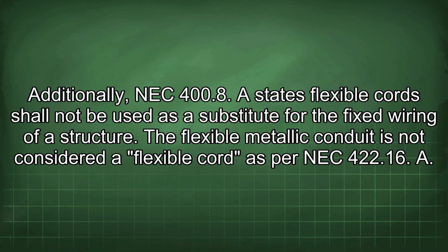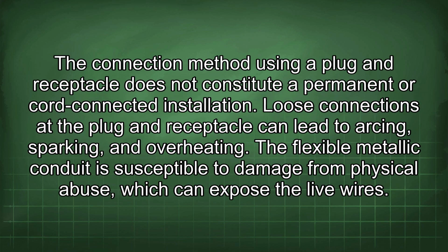Additionally, NEC 400.8 states flexible cord shall not be used as a substitute for the fixed wiring of a structure. The flexible metallic conduit is not considered a flexible cord as per NEC 422.16. The connection method using a plug and receptacle does not constitute a permanent or cord-connected installation. Loose connections at the plug and receptacle can lead to arcing, sparking, and overheating. The flexible metallic conduit is susceptible to damage from physical abuse, which can expose the live wires.